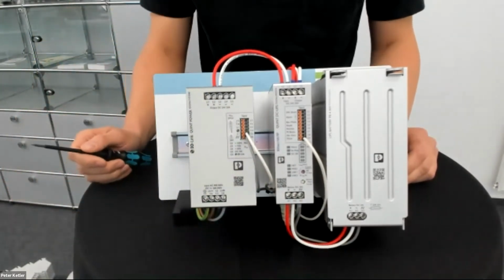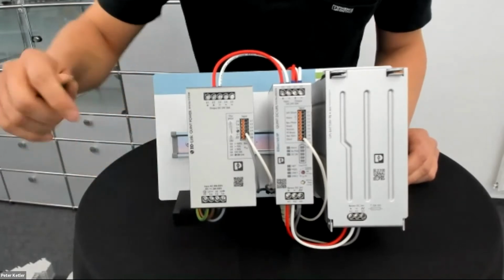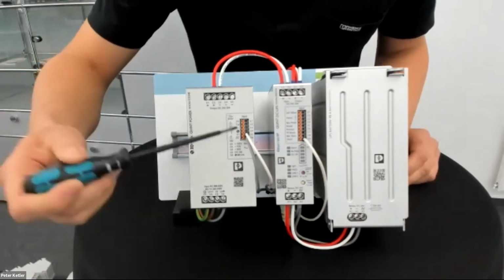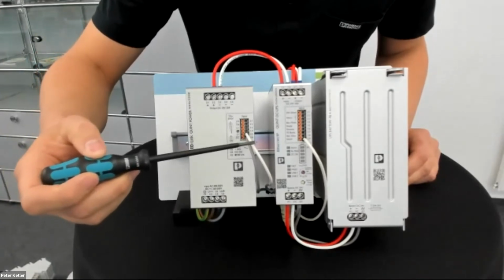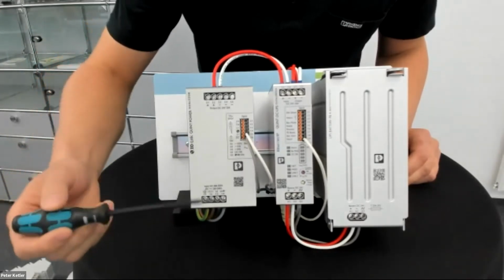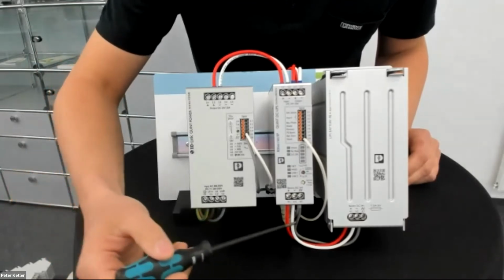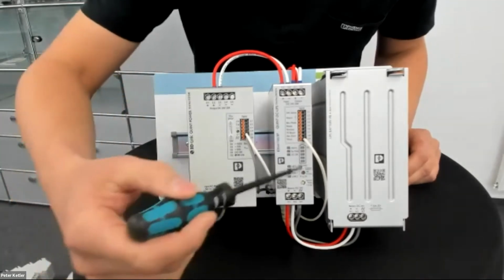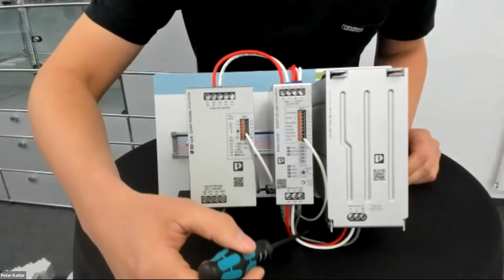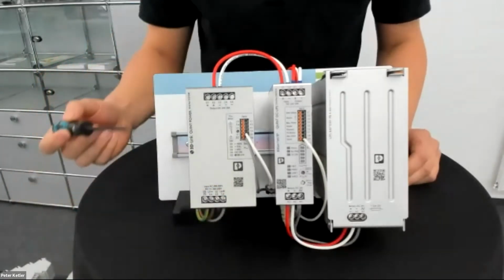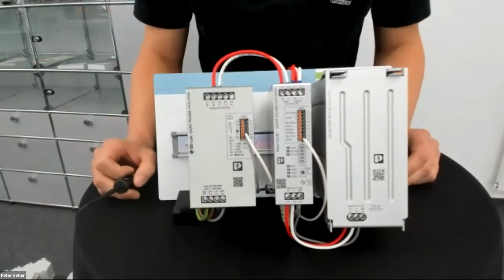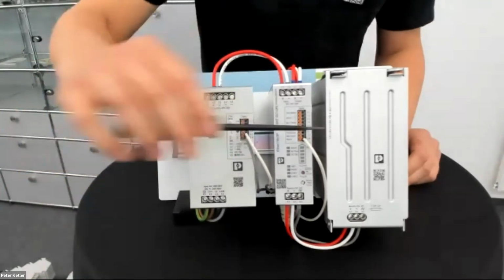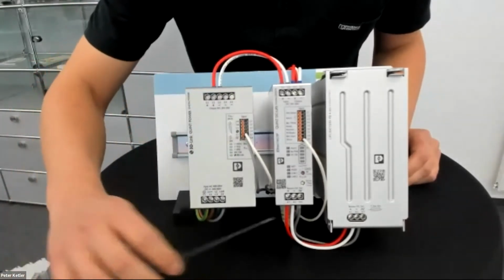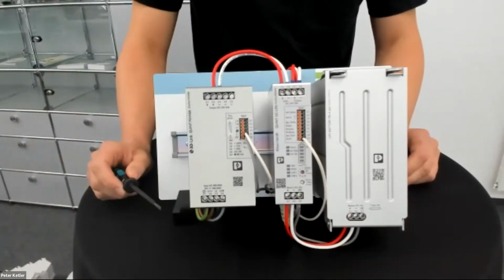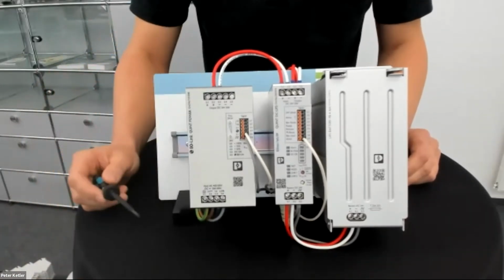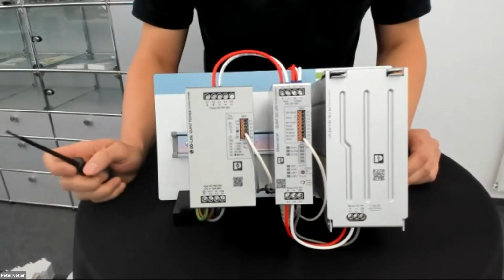So of course, we're talking about communication and information. So we have a data connection here as well. So here you see the system bus connected in white and gray. So this will be connected here to the UPS. And this data wire will also go to the battery. So we have a full data transmission from each component. And then here below, you have 2 ports for the field bus in order to provide the data from the UPS as central gateway.